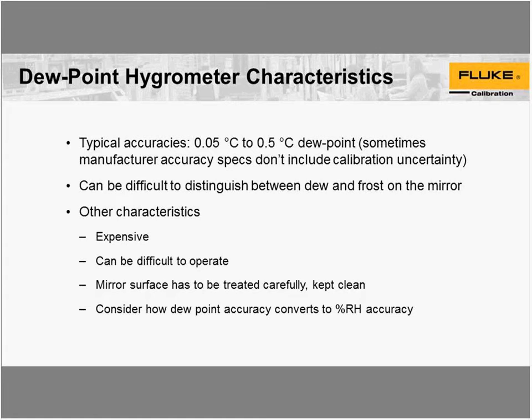They talk about it more in terms of a long-term drift, you know, a 12-month or 1-year repeatability or drift, and then you have to get the chilled mirror calibrated from someone and then add in the uncertainty to that.